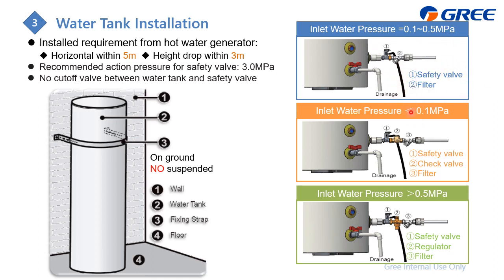And if the pressure is less than 0.1 megapascal, we need to install the check valve, this one. The purpose of this one is just to prevent the water from backflowing to the outside. And if it is higher than 0.5 megapascal, you need to install the regulator to lower the pressure into this range.